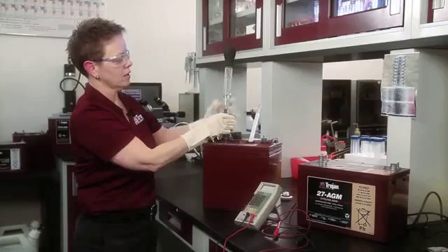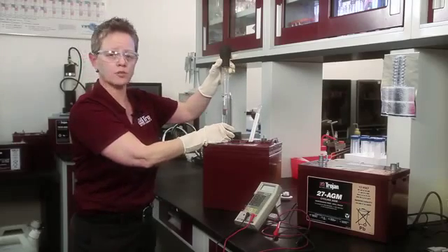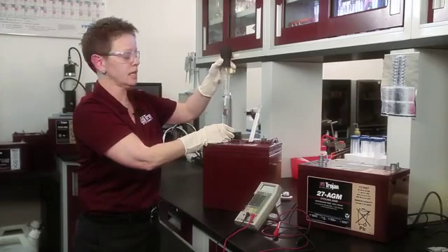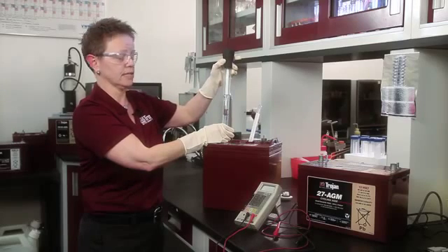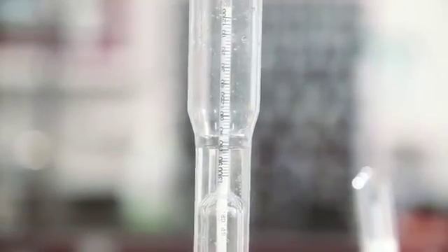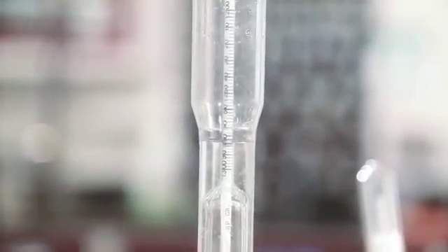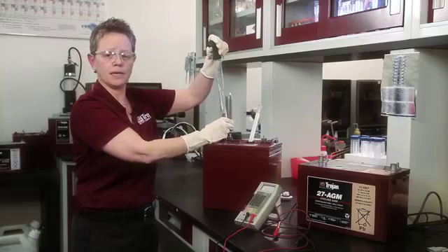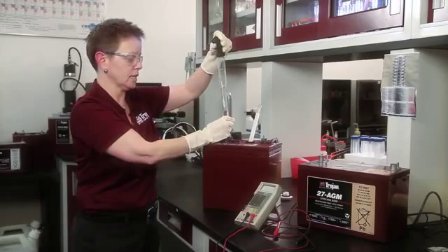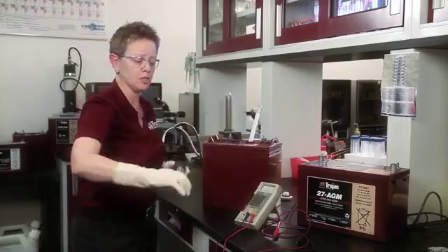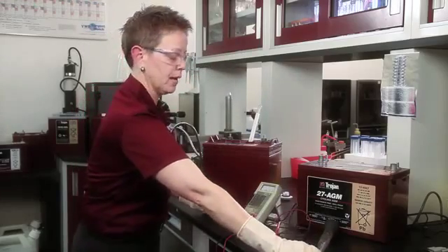You want to make sure that the float that's inside of the hydrometer floats freely and is not stuck to the side like this, as it can give you an errant reading. This reading here, once it is stabilized, is 1.285. That is an acceptable value. You then aspirate the electrolyte back into the cell, being careful not to get anything on you. And you would repeat this procedure for the remaining cells in the battery.